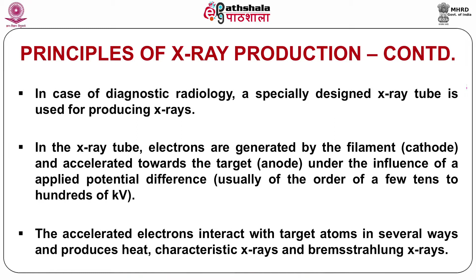In case of diagnostic radiology, a specially designed X-ray tube is used for producing X-rays. In the X-ray tube, electrons are generated by the filament, that is called cathode, and accelerated towards the target, which is called anode, and is usually made from tungsten, which has atomic number Z equal to 74, under the influence of an applied potential difference, usually of the order of a few tens of kV.